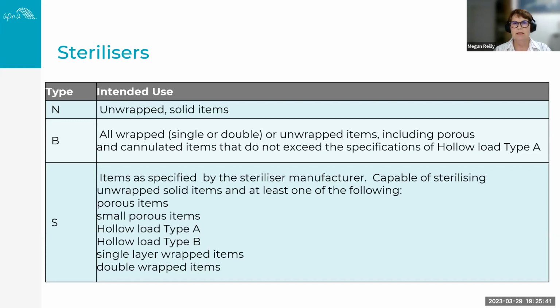The Class B sterilisers are all encompassing. They can be used for all wrapped, single or double, or unwrapped items, and that includes porous and cannulated items that don't exceed the specifications of a hollow A type load. But I would say that most practices are probably using an S-class steriliser. And so these items are actually capable of sterilising unwrapped solid items and at least one of the following. So if you have an S-class, it's really important to know what cycle it can. Can it sterilise porous items, hollow load type A, hollow load type B, single layer wrapped items, or double wrapped items? So whatever you are reprocessing, you need to ensure that the steriliser is capable of sterilising that load.